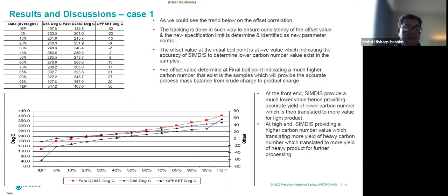So the tracking is done in such a way to ensure the consistency of the offset value, and the new specification limit is determined, identified as a new parameter control. Okay, on the first table on the right side, the offset value at the initial boiling point is a negative value, which indicates, as I mentioned just now, the accuracy of SIMDIS in determining lower carbon numbers, as low as C3. And the positive offset value at the final boiling point indicates a much higher carbon number that exists in the samples, which will provide an accurate process mass balance for crude charge to product charge.